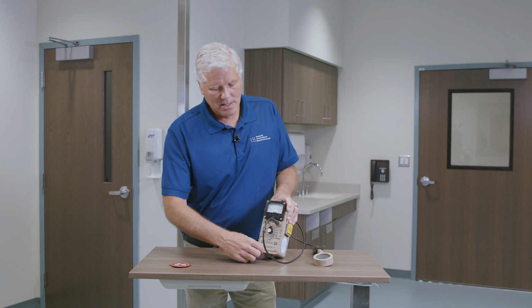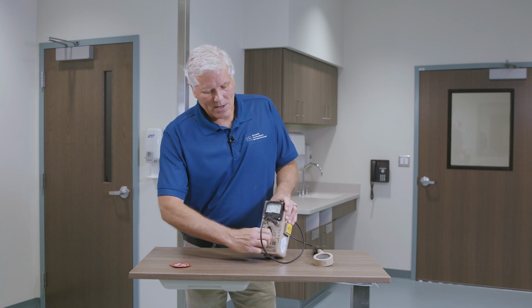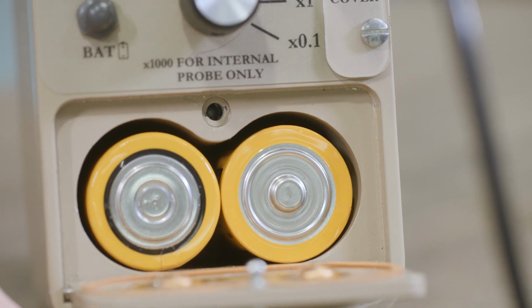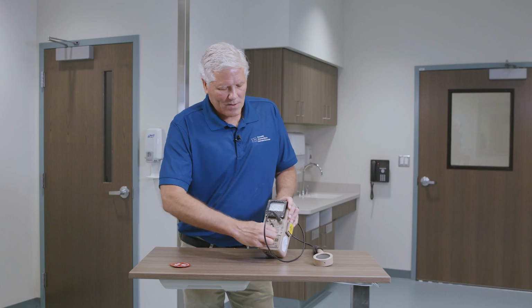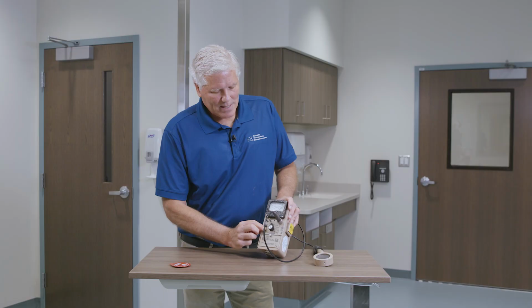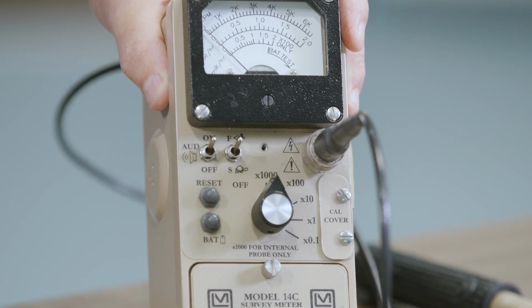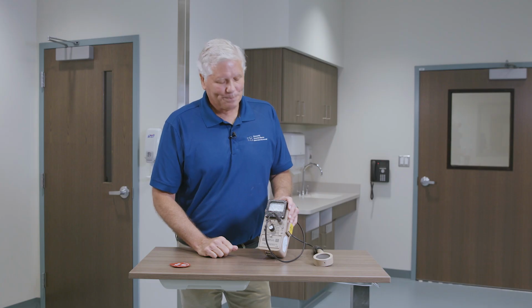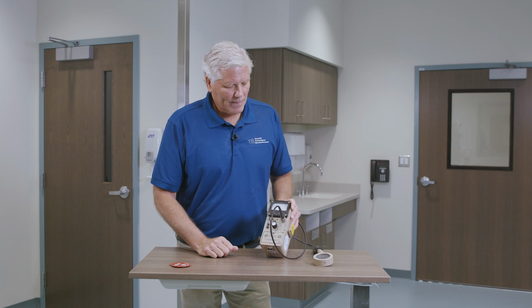very simple process. All we need to do is open up the battery compartment. And in this case, you can see it's just 2 D batteries to replace. Replace the batteries, go ahead and do the bat test again. If it doesn't go into the bat test, it's not usable. But in most cases, it will be.